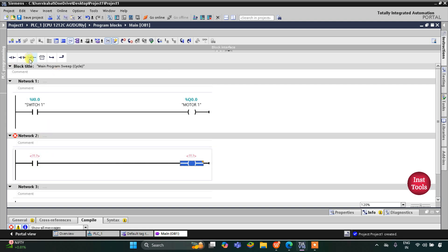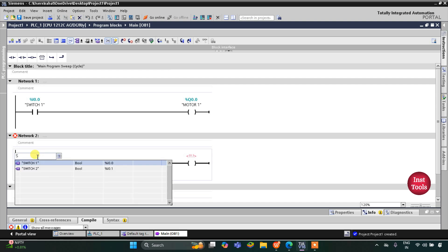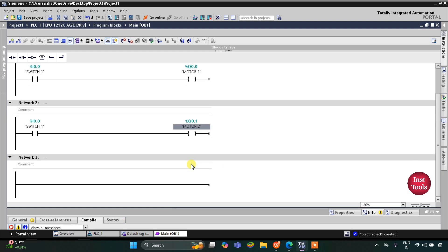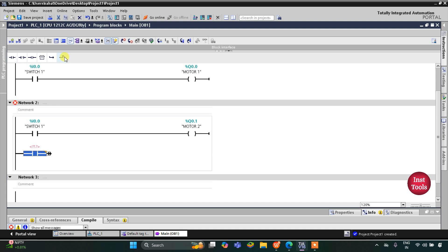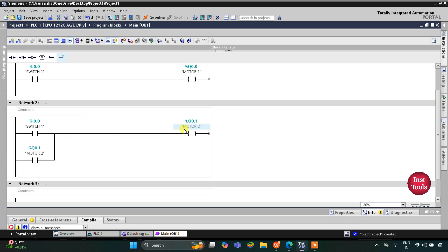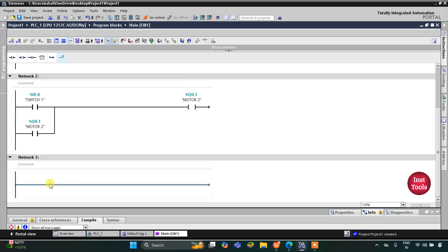For Motor 2 I will insert a normally open contact and a coil. This normally open contact is Switch 1. When Switch 1 is off, Motor 2 should remain on — for that we will latch Motor 2. I will open the branch, add a normally open contact, and close the branch. This normally open contact will be Motor 2, so when Switch 1 is turned off, Motor 2 still remains on. Similarly, I will insert a normally open contact for Switch 2.